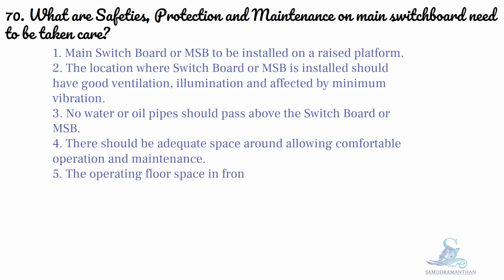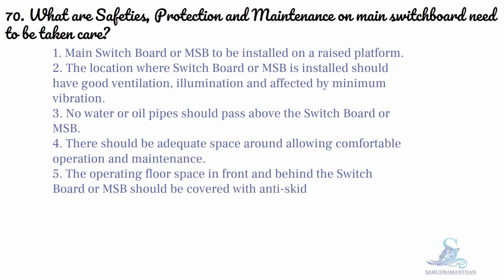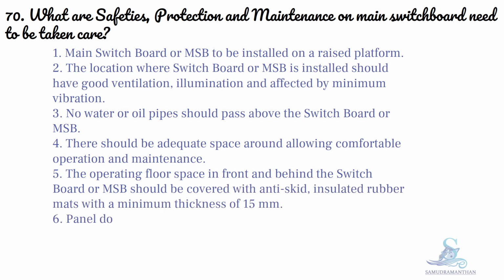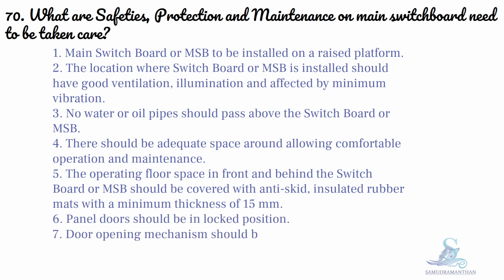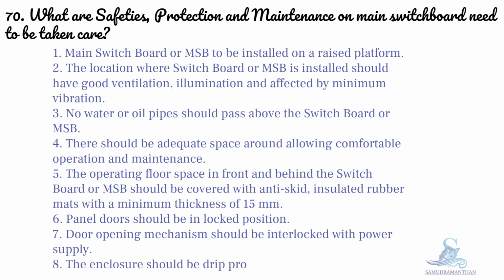The operating floor space in front of and behind the switchboard or MSB should be covered with anti-skid insulated rubber mats with a minimum thickness of 15 mm. Panel doors should be in locked position. The door opening mechanism should be interlocked with the power supply. The enclosure should be drip proof.